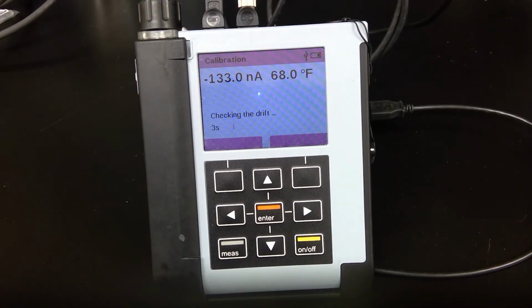Now, DO probes take a little bit of time to stabilize, so we may see anywhere from 30 to 60 seconds of stabilization. And once we have the calibration completed on this DO probe, it will be ready to be carried out and do a hot swap with the probe that's already in the field.